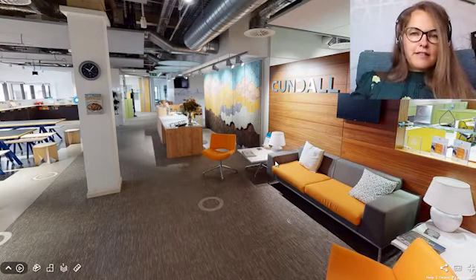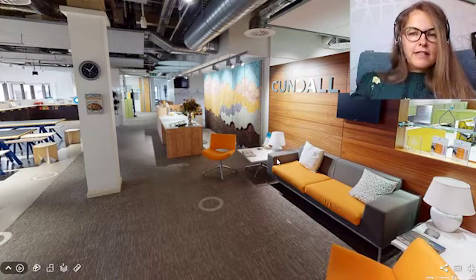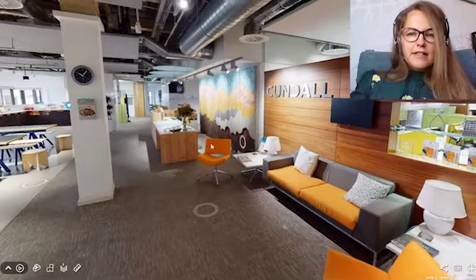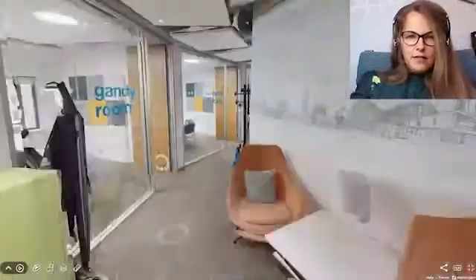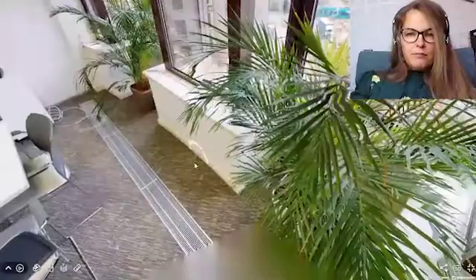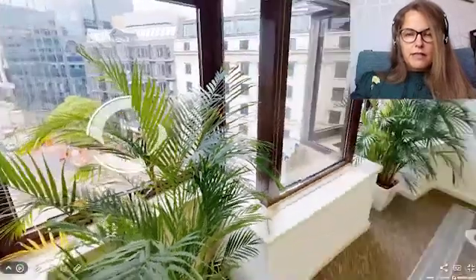Selection of cleaning products is key to reducing indoor exposure. So air quality tends to be worse during periods of high traffic or where construction activities are taking place locally. So frequent review of the air quality index enables alerts to be displayed in reception when ambient air quality exceeds a set criteria, such as more than 51 parts per billion ozone or greater than 50 micrograms of PM10, or also if our temperature is above or below 8 degrees Celsius of our set temperature.